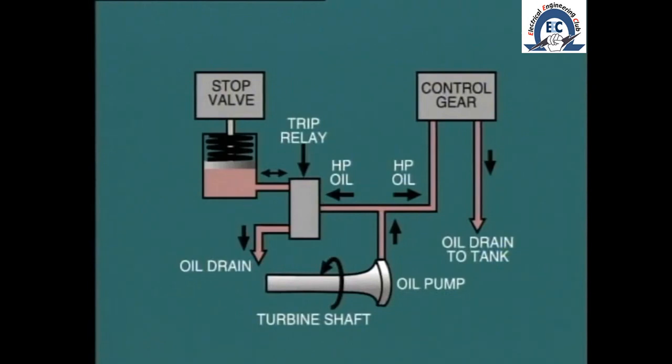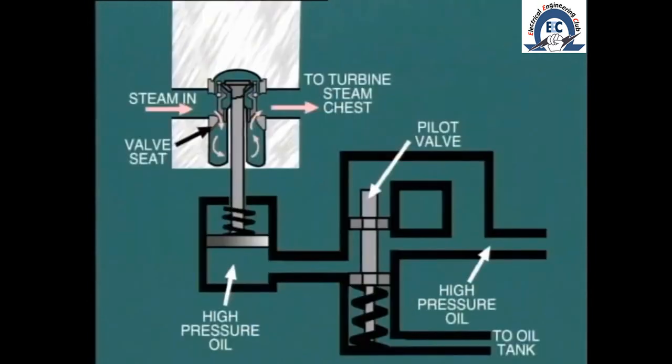The same hydraulic oil supply is used to operate the turbine stop valve. One common arrangement is shown here. During normal operation, the pilot valve is open and allows high-pressure oil to enter the space below the piston and hold the stop valve open against the compression of this high-powered spring.